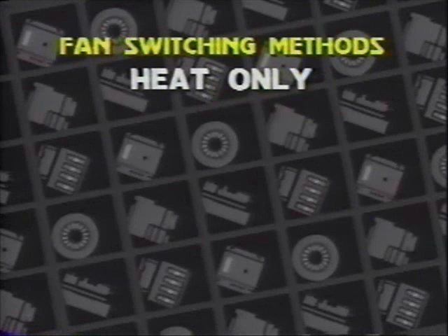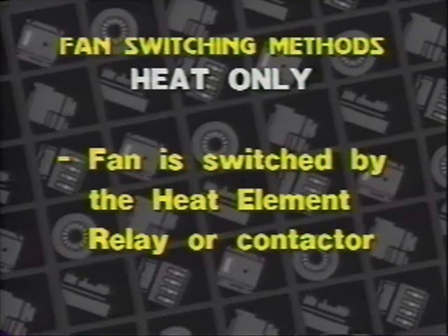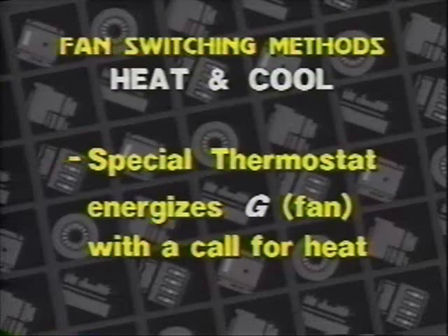2 basic fan switching methods are used. In heat-only systems, the fan is usually switched by the same relay or contactor that controls the heat elements. In heat-cool systems, you might find a special thermostat that energizes the G, or fan terminal, with every call for heat.